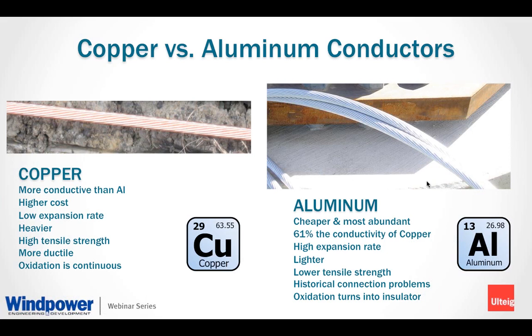So that means if you have a copper cable with the same size diameter as a pure aluminum cable, you're going to be able to carry tremendously more power through the copper versus the aluminum. This is the major advantage of copper, it's just more conductive. Over the years, people have shied away from aluminum just because properly making connections on aluminum is more difficult. One of the main things you need to consider is properly cleaning before making splices or connections throughout the wind farm.